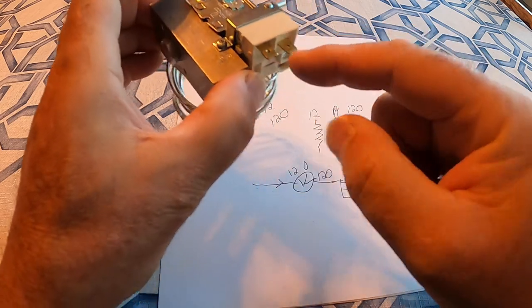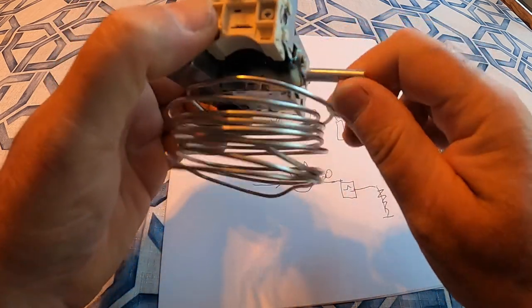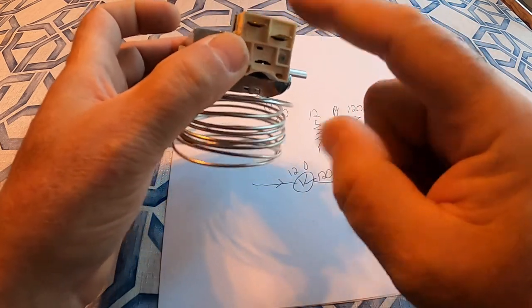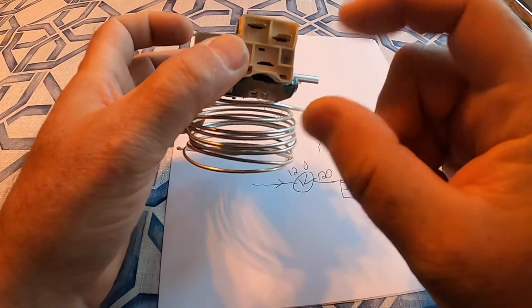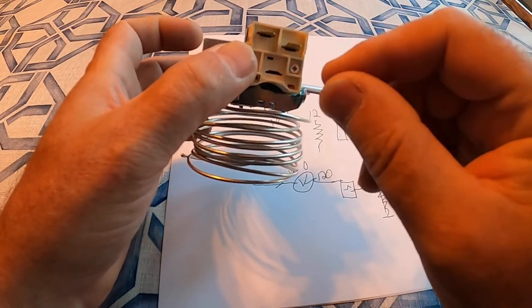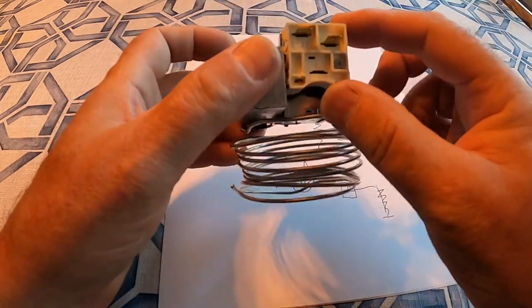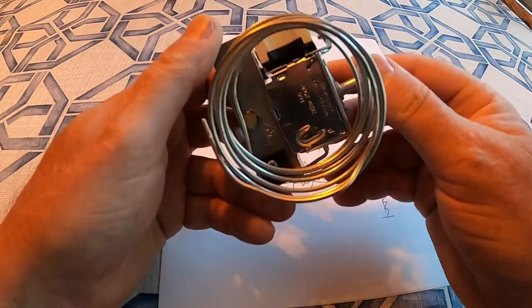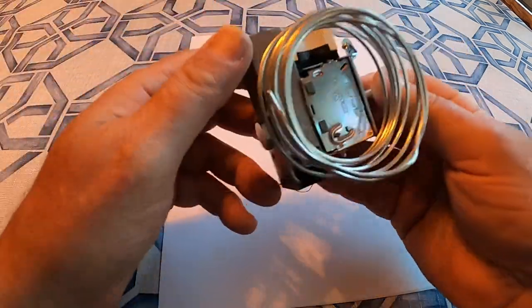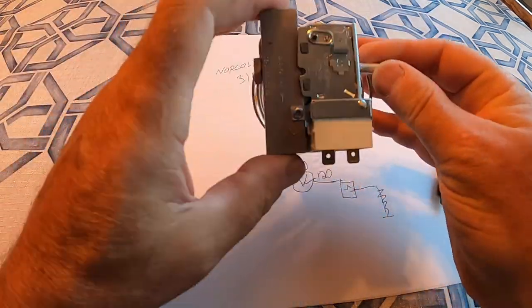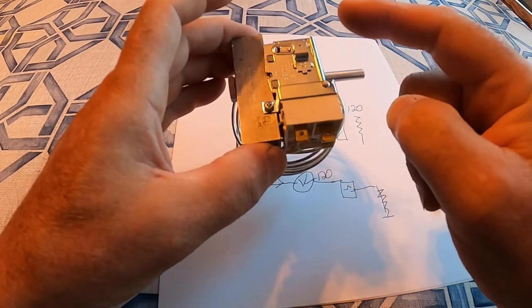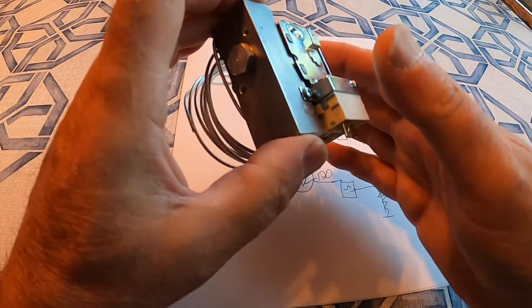In my situation, these two contacts, no matter what position you put the thermostat in, they don't make contact anymore. They're pitted or burned out or they're stuck or something in the one that's in the trailer. So we're going to go out to the trailer and we're going to take out that bad one and put this one in. It's a pretty simple process. I thought you might want to see it. So let's head out there and I'll show you what the original one looks like and how we're going to put this one in.